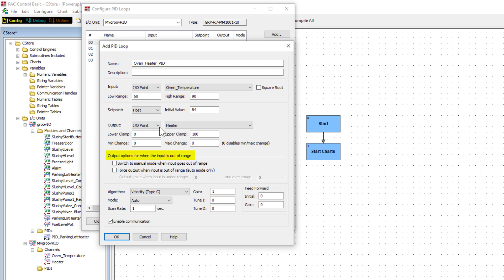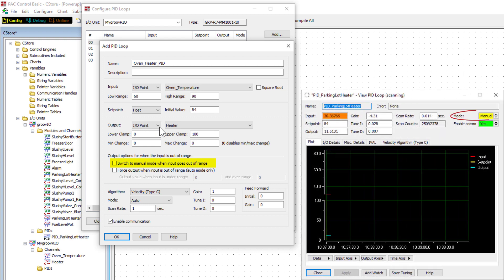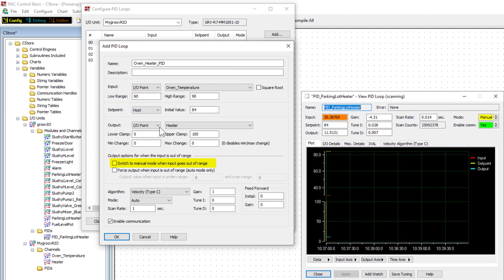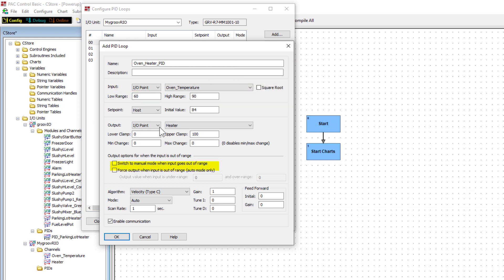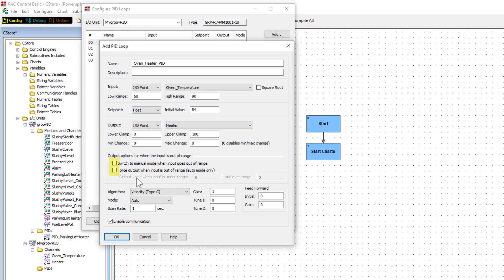Output options when input is out of range. These options let you manipulate the PID in case the input goes out of range. The first option, switch to manual mode when input goes out of range, lets you switch the PID to manual mode until an operator or PAC control logic assumes control. Another option is to select the force output when input is out of range. This is only in auto mode. This lets you set the output to a minimum and maximum value when the input goes under and over range respectively. Leave both of these options unchecked.